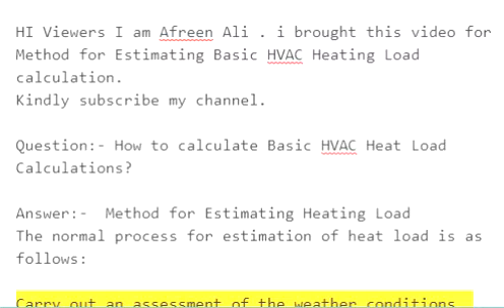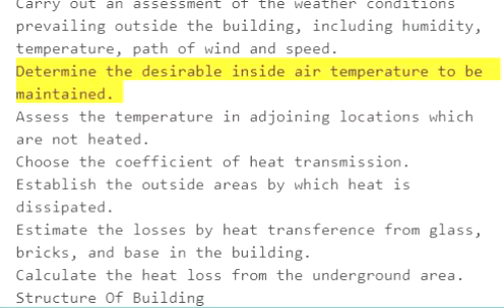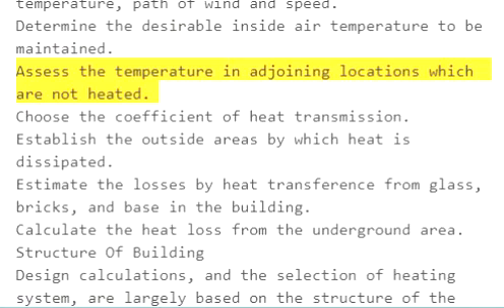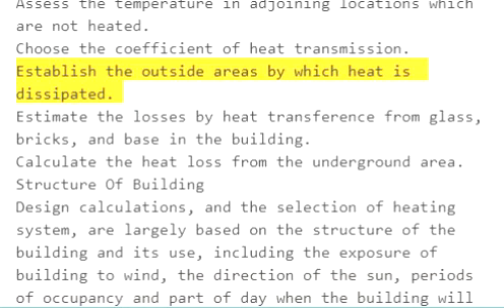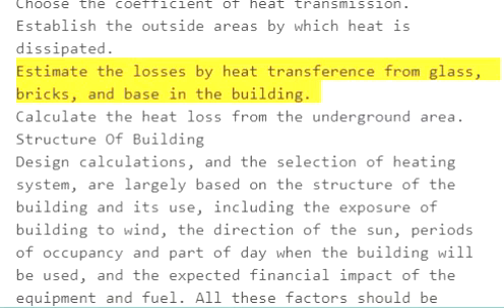Carry out an assessment of the weather conditions prevailing outside the building, including humidity, temperature, path of wind and speed. Determine the desirable inside air temperature to be maintained. Assess the temperature in adjoining locations which are not heated. Choose the coefficient of heat transmission. Establish the outside areas by which heat is dissipated. Estimate the losses by heat transference from glass, bricks, and base in the building.